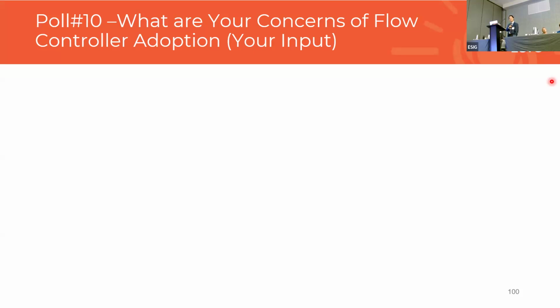Just curious about protection. You've got reclosers, you've got all kinds of devices moving. We've seen the industry inundated with interactions between inverters. So you've got a distribution feeder with batteries, with solar. How is this going to respond to faults? And how is it going to respond to getting multiple reclosures back into the fault?